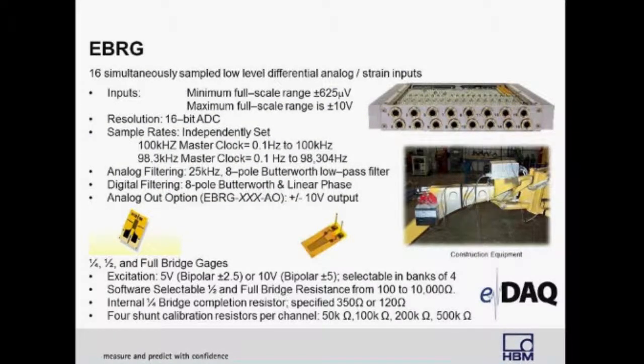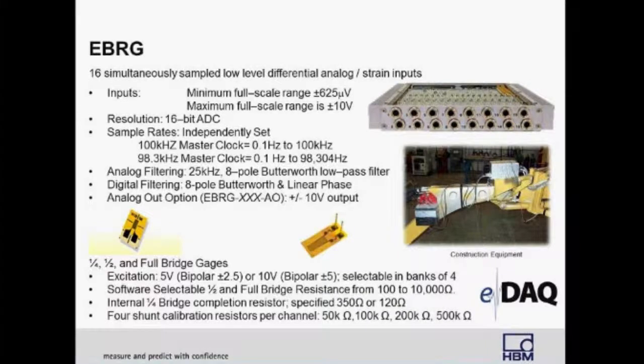The eBridge layer with 16-bit resolution can simultaneously sample 16 channels of low-level differential analog inputs. It is an excellent choice for measuring transducers with low-level signals or strain gauges. It has bipolar excitation capable of 5 and 10 volts. The eBridge can also measure quarter-bridge, half-bridge, and full-bridge gauges. It has internal completion for quarter-bridge strain gauges of the 120 and 350-ohm variety and four shunt calibrators per channel for 50k, 100k, 200k, and 500k-ohm shunts. The eBridge also has an optional analog out module that can output signals up to plus or minus 10 volts, typically used to supply a signal to some type of controller.